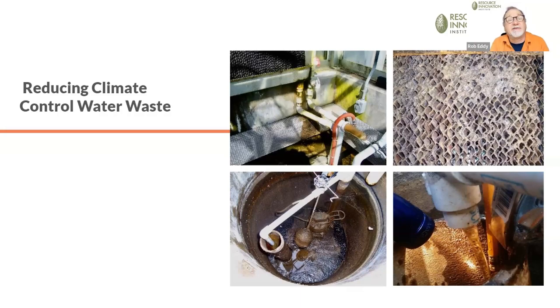And in this case, and this is one of my greenhouses, so I'm not putting anyone down, cottonwood seeds that were floating in the air were sucked in and landed on the back of that pad, then it got calcified, so it cut down on the effectiveness of the pads. The empty reservoir you see here is a pretty scary place to work. It's slimy, you're down on your knees in cement, and it's not very glamorous work.